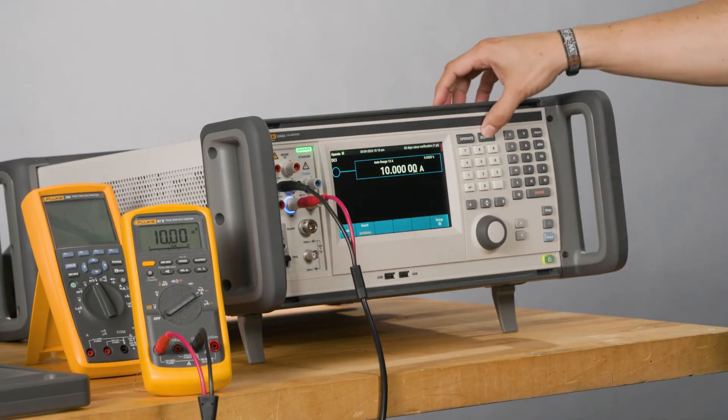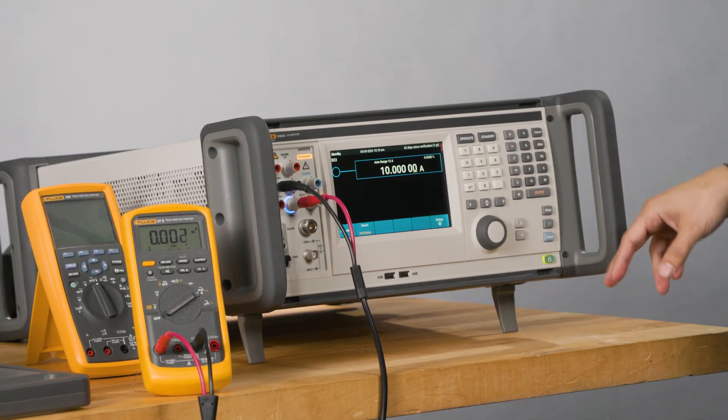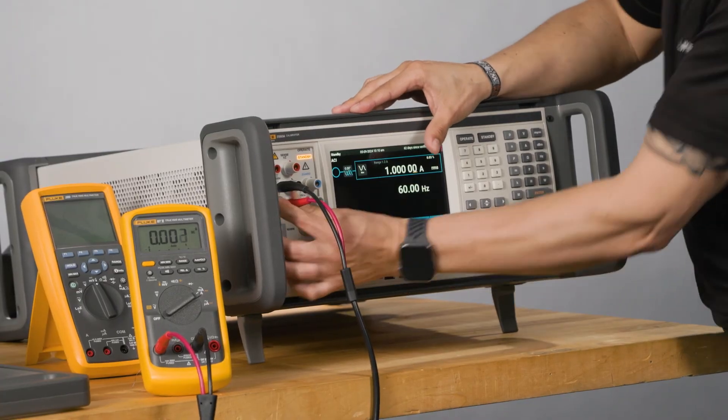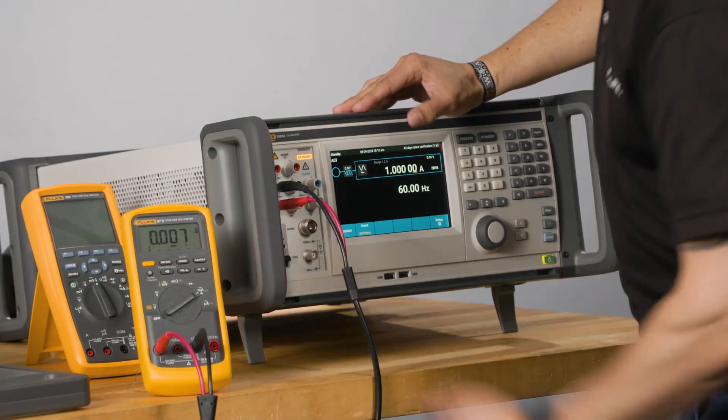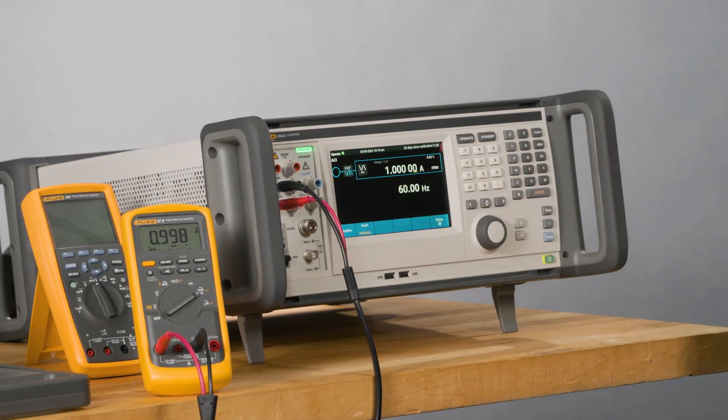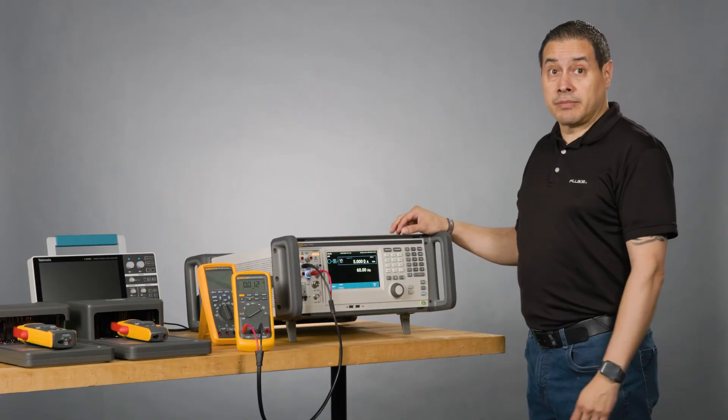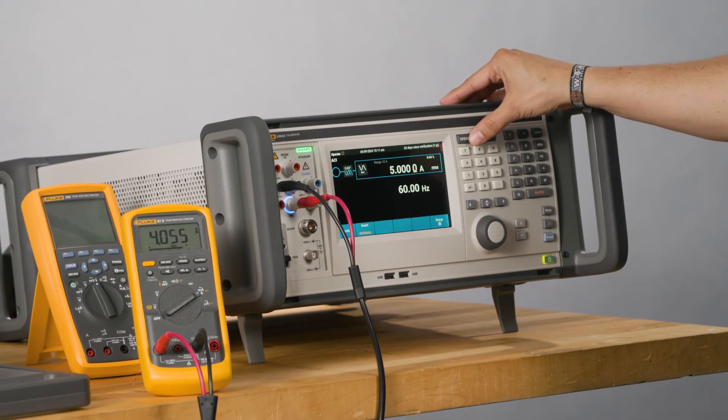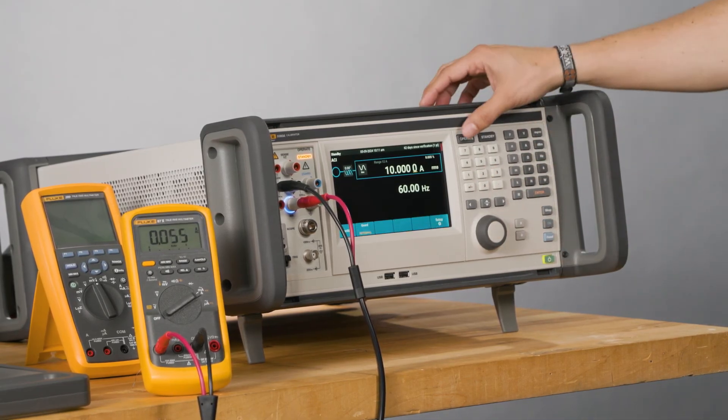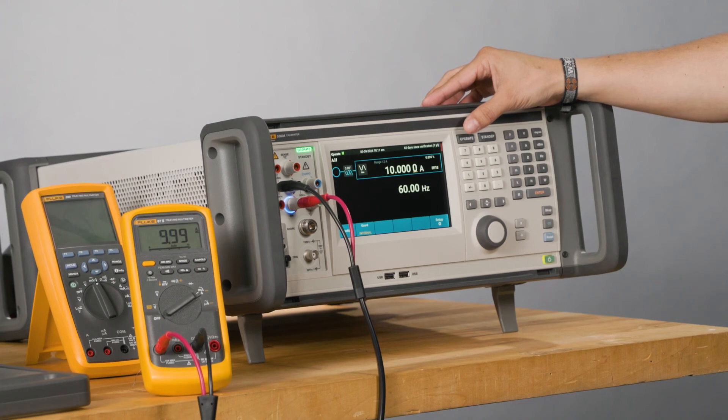10.00. I'm good. Next, I'll be jumping to AC current. So one amp, 60 hertz. I need to check the post. Then change to AC. My calibrator will tell me which post I need to use. So pay attention to the lights. 5 amps. Good. Perfect. Then last point. 10 amps in this case. And I'm done.